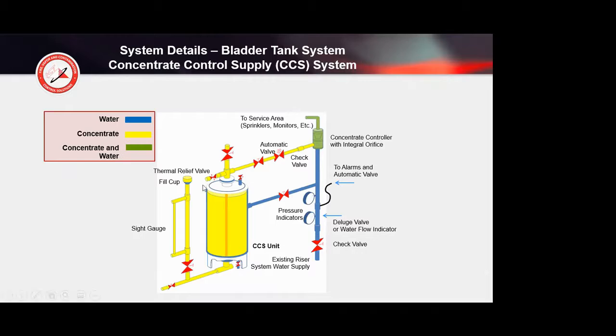What keeps this agent from automatically discharging from the tank is right here, a hydraulic actuated control valve, and we'll have a piece of tubing that comes down to the deluge valve. So once the deluge valve opens, it sends water up here to hydraulically open this valve to allow the agent to flow.